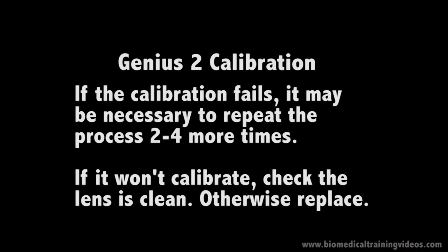If the calibration fails, it may be necessary to repeat it up to 2, 3, maybe even 4 times. If it won't recalibrate, it's worth just checking that the lens is clean or going through and cleaning it again, otherwise the unit may require replacement, so contact your supplier with that.